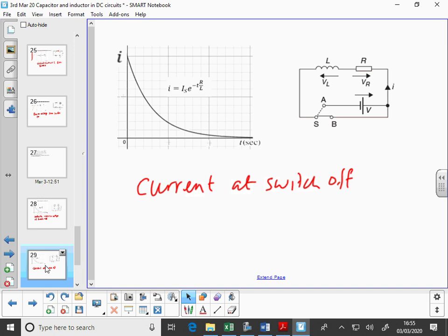So if you look at normal switches for lights, for instance, you'll find they're rated so many amps resistive load, less current inductive load, and that's because the inductive load is going to cause arcing when you open the terminals, and that can be quite destructive.